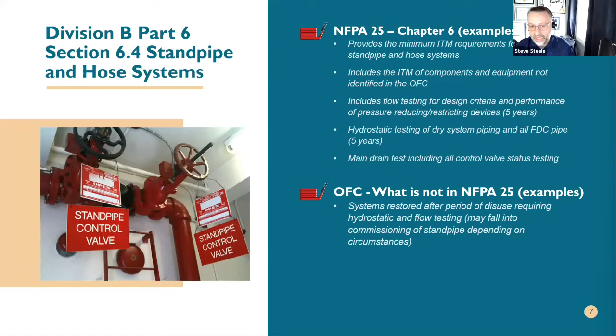There are existing means for any fire protection system. If you take it out of service, it must be identified to the AHJ. So it would almost fall into that of commissioning or recommissioning that system when you put it back into service. So not only standpipe, but sprinkler systems themselves usually entail a lot of that paperwork, or at least identification from owner to AHJ. So that may take some review as well by the powers that be to make sure that it is not just disregarded, that there's some language, or at least assurance that it's covered when you have a disuse of a standpipe system.